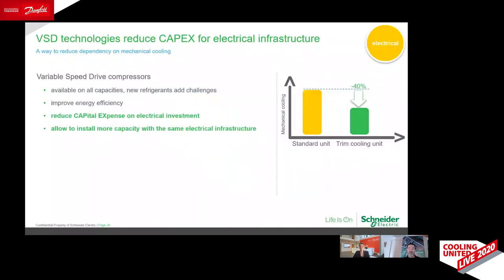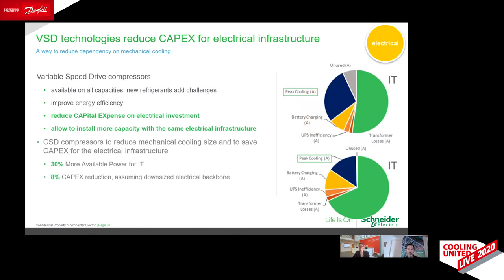So again, talking about variable speed and the electrical infrastructure, variable speed drive compressors are certainly more expensive than traditional compressors. You have the inverter, so there is something more on the unit. However, there is a capital expense reduction. The data center is less expensive. So you can decide to use this as a reduction of the capital expense, or to keep the capital expense and extend the amperage you have for the infrastructure. This is a holistic approach from the electrical point of view.